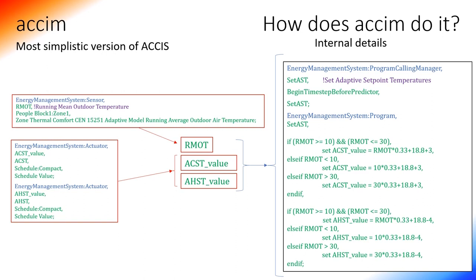Then, an EMS program and a program calling manager object are added, which control the calculation of the values and setting of the actuators depending on the RMOT sensor, with two if blocks for the heating and cooling set point temperatures. This provides the first of the two main features of ACCIM.